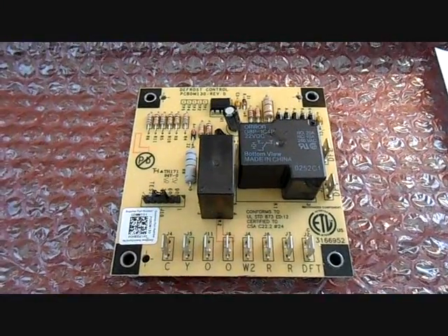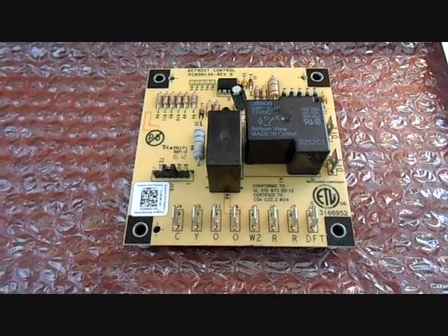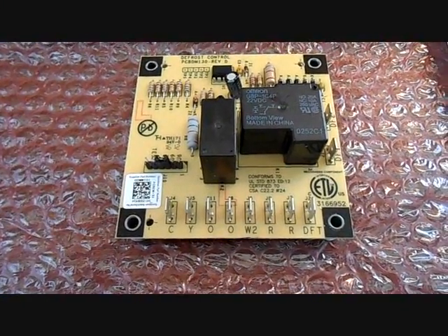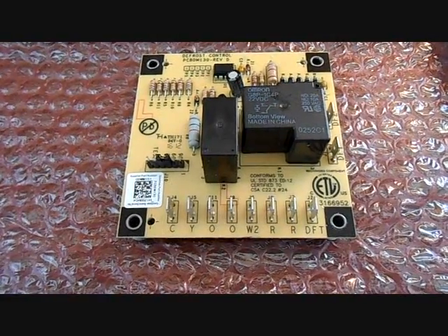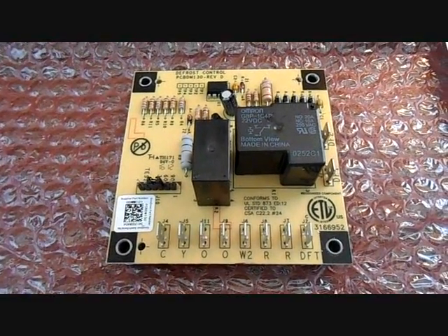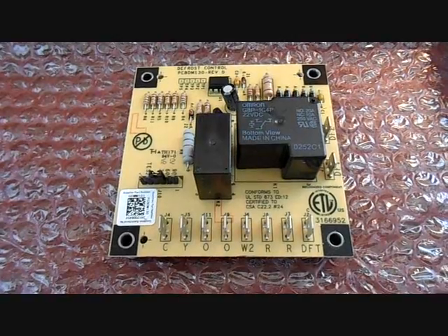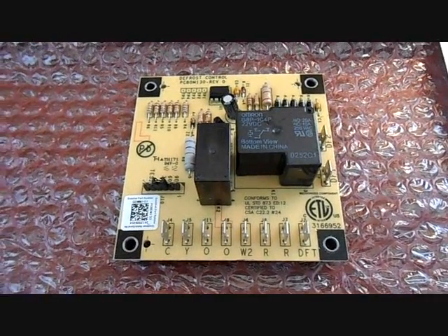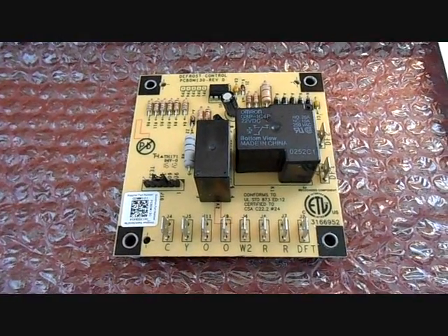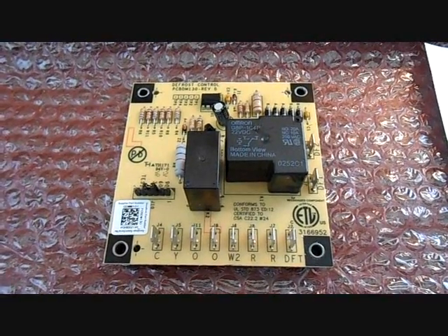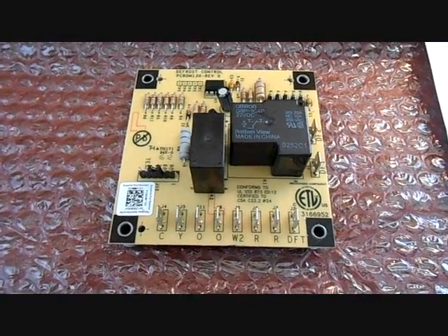Okay, today we're going to talk about a Goodman defrost controller. It's PCBDM130. And this is in a whole lot of Goodman stuff. It's been in a similar model all the way back into the 1990s. They've been using the same one for a while. It's just a low-cost board.